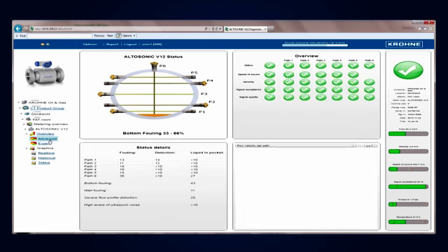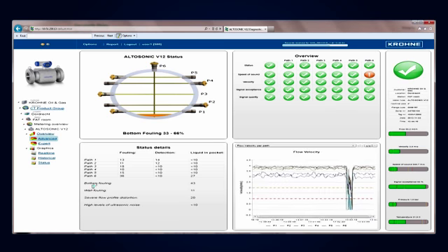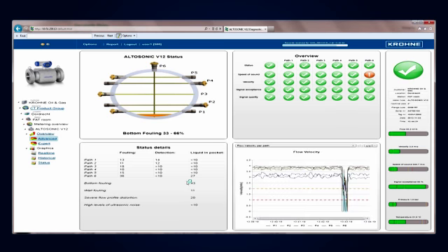In the advanced mode, we see the bottom fouling has gone to 43. So it's no longer below 33, it's above, it's 43, meaning we give a warning for bottom fouling, which you see here. Also, you see here the speed of sound of path 6 deviates. There is a warning, again the reason being the too high velocity, because the bounce is now done on the piece of tape.